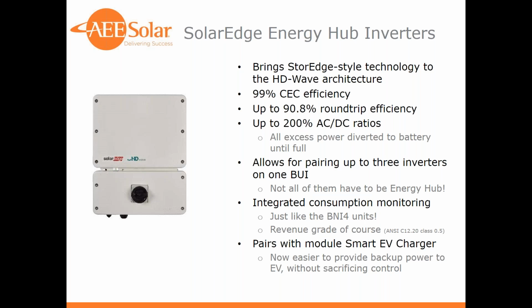For example, I've got an EV charger at home. It takes a 40 amp connection and will pull up to 32 amps. Right there, we're basically over the output rating of a single SolarEdge unit. So for me to have backed up my EV charger, I would have needed to do some programming in my car to make sure it doesn't pull more than a certain amount of amps, and just hope that in backup mode I didn't have other loads that would put the unit into overpower protection.